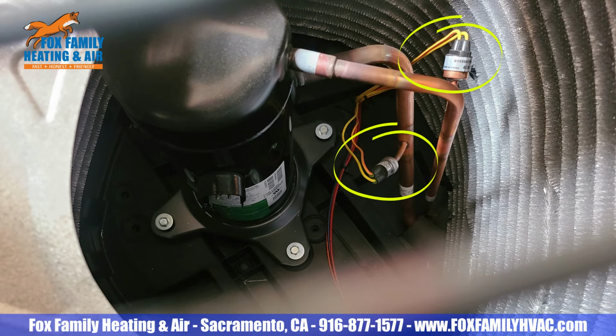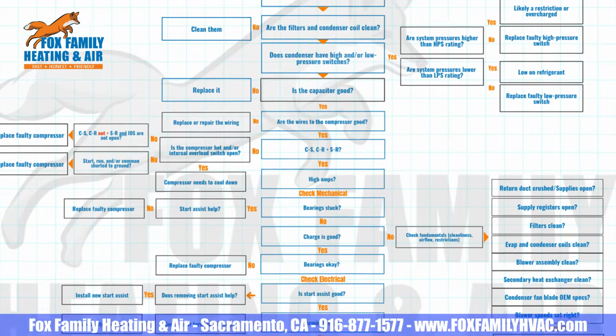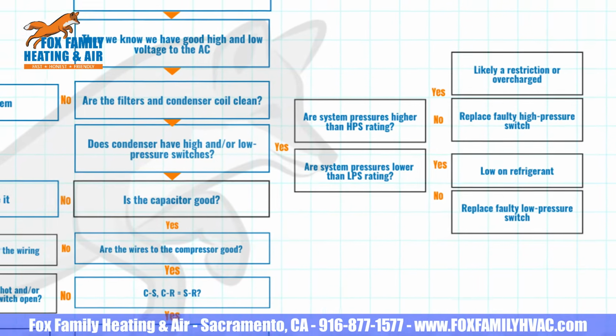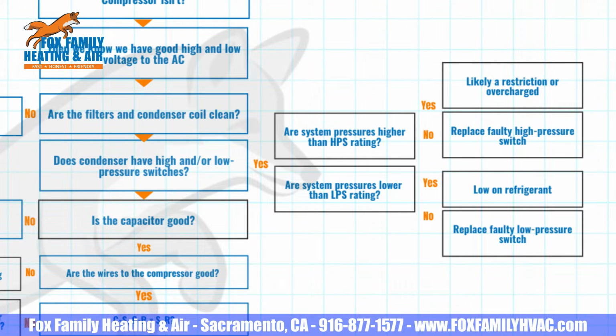contactor. First, let's check for any high or low pressure switches in the refrigerant lines around the bottom of the condenser shell, below the fan. Some ACs have them and some don't. But if so, is the pressure in the system higher than the rating on the high side pressure switch? If it's not, then you'll need to replace the faulty pressure switch. If yes, the pressure is higher, then there's likely a restriction in the system or the system could be overcharged. Same with the low side pressure switch. Is the pressure in the system lower than the rating on the low side pressure switch? If it's not, then replace the low side pressure switch. If it is and the pressure is lower, then you're low on charge. Charge it up and follow your company's process for finding leaks.